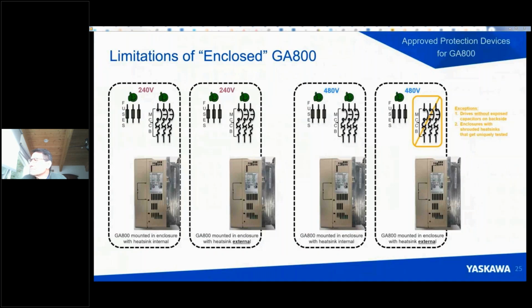Okay. Now the exception is drives without exposed capacitors on the backside, and this is something we will be clear about in our instructions as well. For those, you could actually do this with no problem. As a matter of fact, we will make our cabinet designs this way ourselves: if capacitors are not on the back side of the drive, there's no problem in having the heatsink external, even when using a circuit breaker for protection.